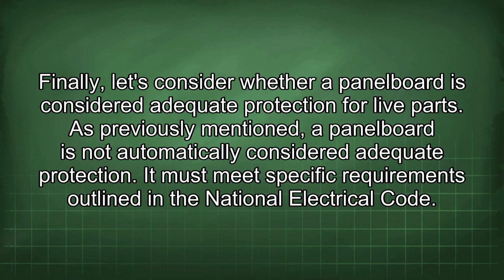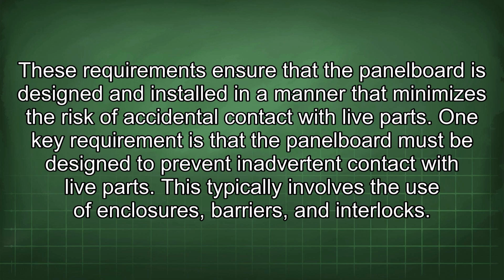Finally, let's consider whether a panel board is considered adequate protection for live parts. As previously mentioned, a panel board is not automatically considered adequate protection. It must meet specific requirements outlined in the National Electrical Code. These requirements ensure that the panel board is designed and installed in a manner that minimizes the risk of accidental contact with live parts. One key requirement is that the panel board must be designed to prevent inadvertent contact with live parts. This typically involves the use of enclosures, barriers, and interlocks.